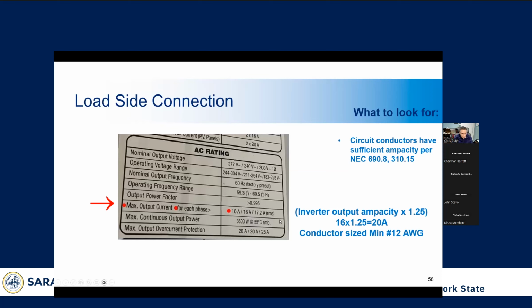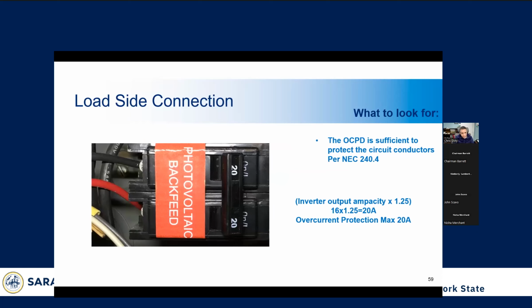And so to figure this out, you want to look at the inverter nameplate, which shows the max output current here. You want to ensure that you size the breaker and the wiring to hold 125% of the rated output ampacity of the inverter. And this is crucial to get right, because if you undersize the wire, you can cause dangerous situations where the wires will overheat, or you could cause fires or things like that.